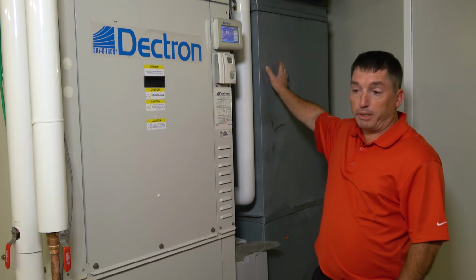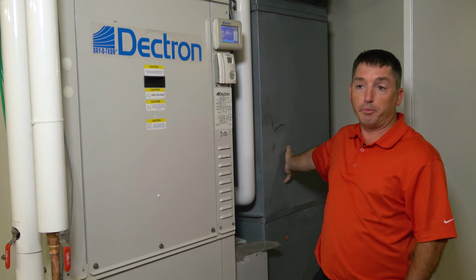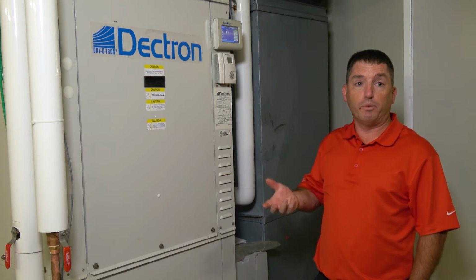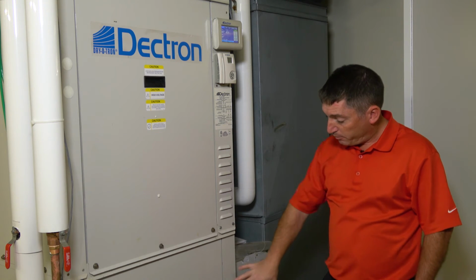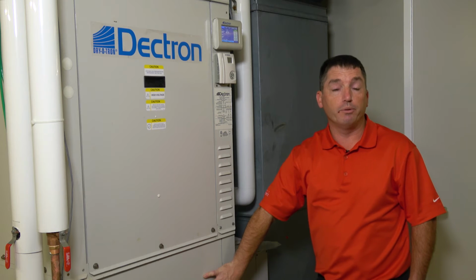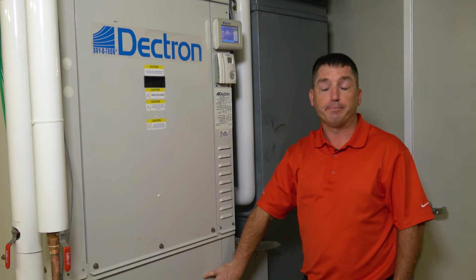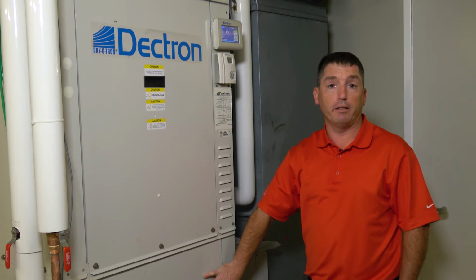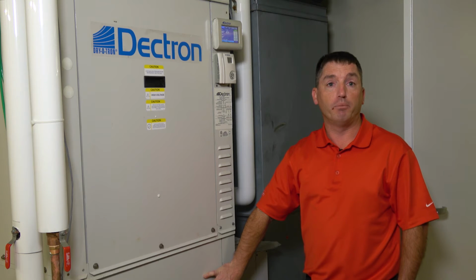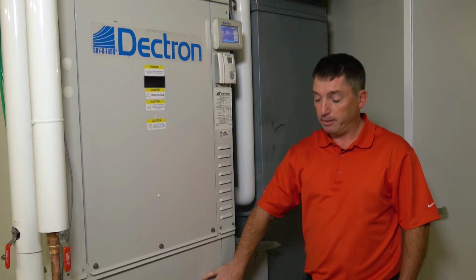Okay, so we bring return air from the pool behind me. That's going to be warm, moist air. We bring it into the unit. We run it through an evaporator coil where we're going to cool that air and try and condense as much moisture as we can out of it.